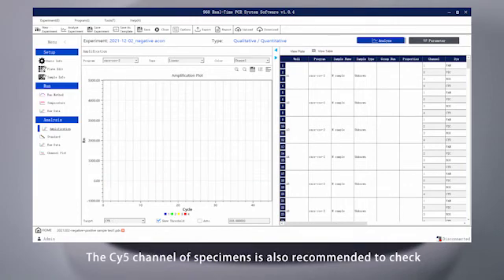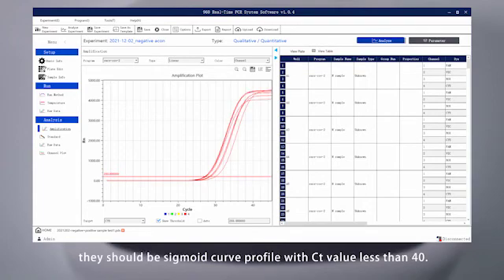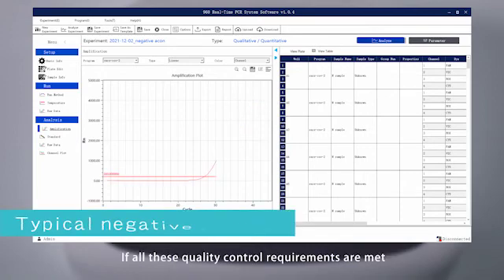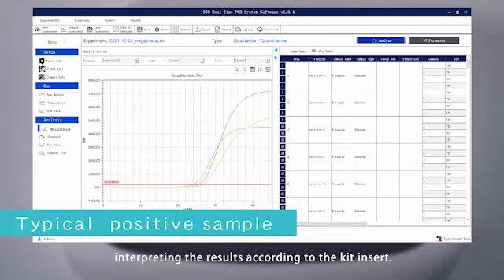The CY5 channel of specimens is also recommended to check. They should be sigmoid curve profile with CT value less than 40. If all these quality control requirements are met, interpret the results according to the kit insert.